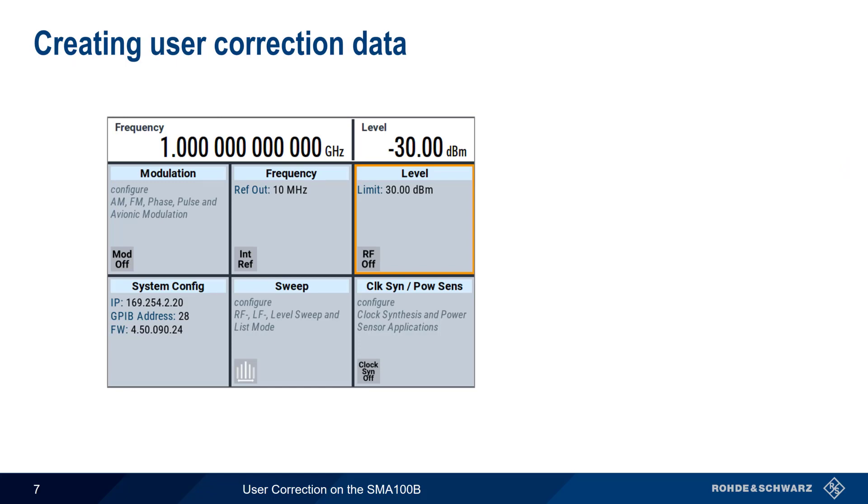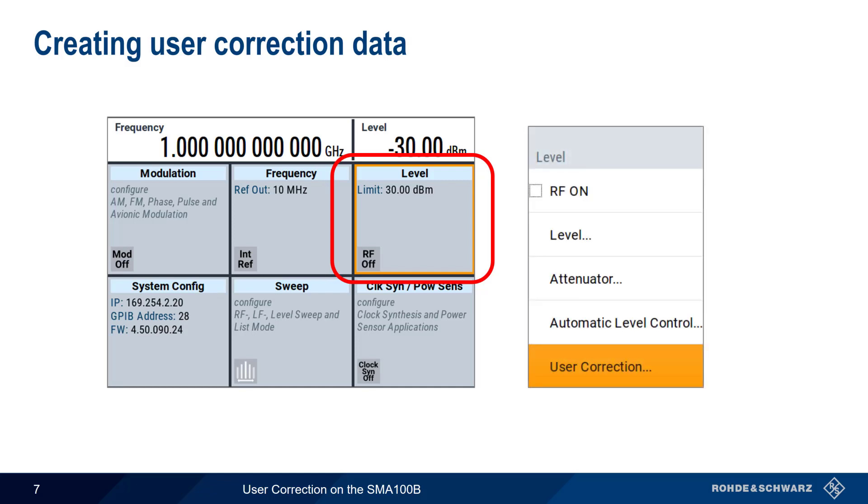The first step is creating the user correction data. We're going to assume that at least one NRP power sensor is connected, mapped, and ready for operation. We'll start by creating a new user data correction file by first clicking on Level in the main SMA100B GUI and then selecting User Correction.